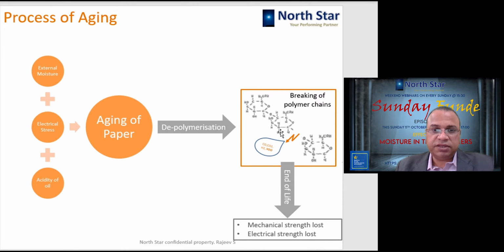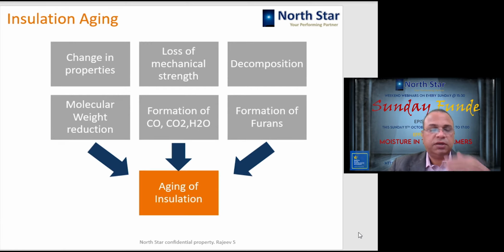Aging of the paper is nothing but depolymerization, and this depolymerization breaks the polymer chains as we have seen, and it releases carbon monoxide, carbon dioxide, hydrogen, and water. So this water gets released, okay, and because of this process, because of this depolymerization or decomposition of the insulation, the mechanical strength is lost, and as a result electrical strength also gets weakened. So this is how the aging of the insulation is happening in the transformer.